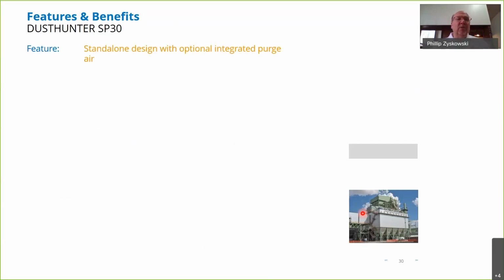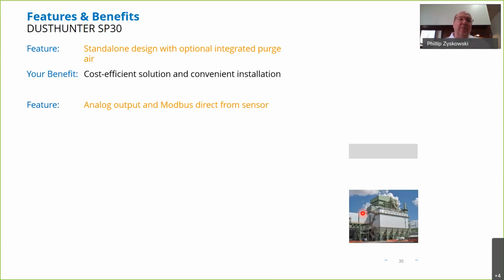So in conclusion, it's a standalone design. So it's very simple, cost efficient. You don't need a lot of extra bells and whistles. We've got both analog output and Modbus that would come directly from the sensor without having to go to any type of alternate or extra piece or box. So that gives you very easy commissioning and startup.